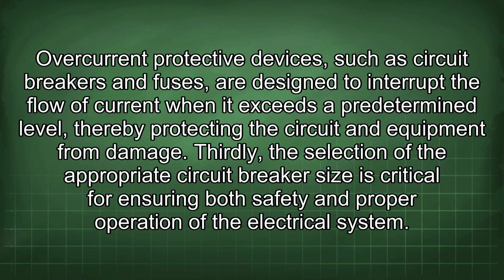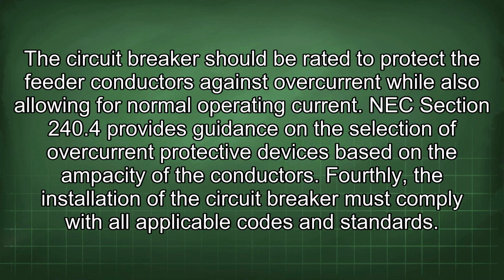Thirdly, the selection of the appropriate circuit breaker size is critical for ensuring both safety and proper operation of the electrical system. The circuit breaker should be rated to protect the feeder conductors against overcurrent while also allowing for normal operating current. NEC Section 240.4 provides guidance on the selection of overcurrent protective devices based on the ampacity of the conductors. Fourthly, the installation of the circuit breaker must comply with all applicable codes and standards.